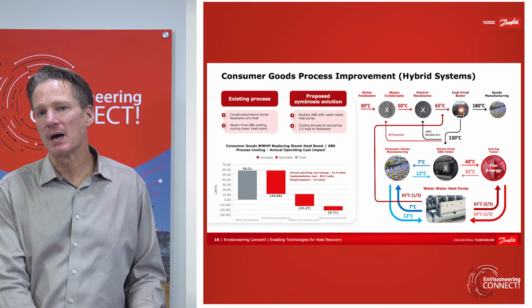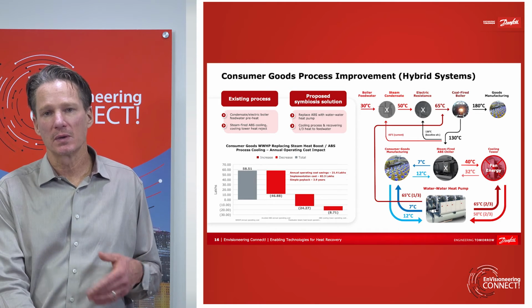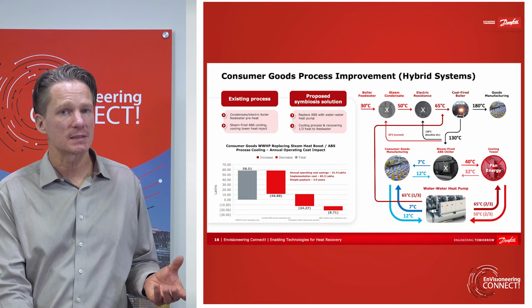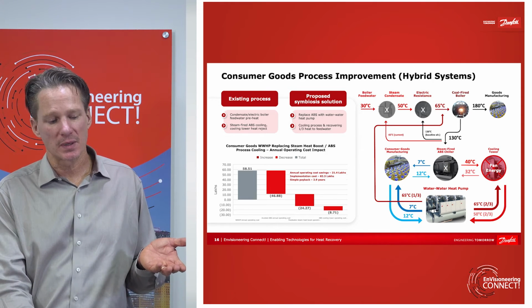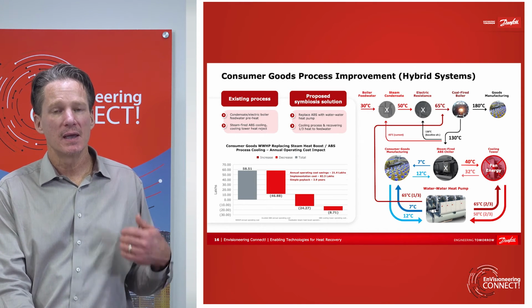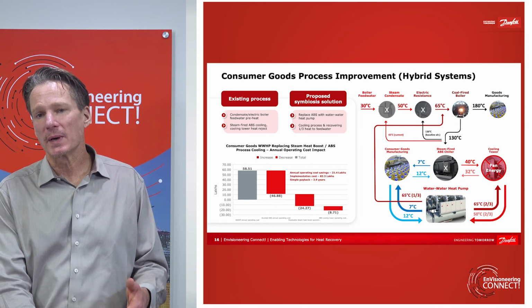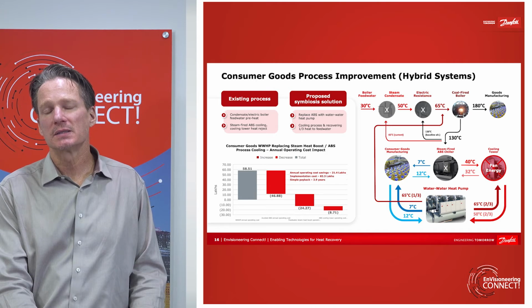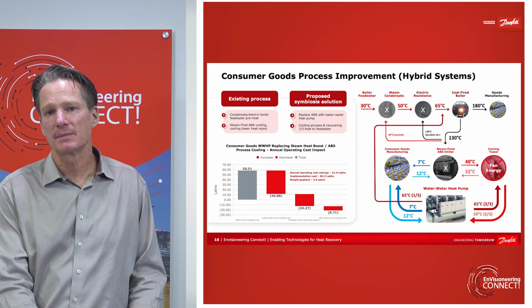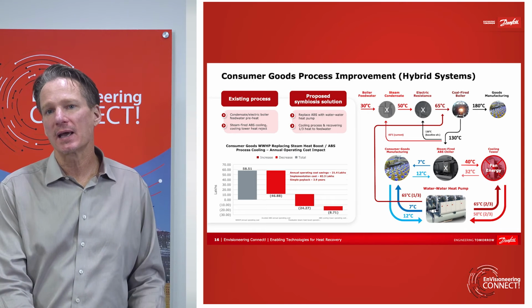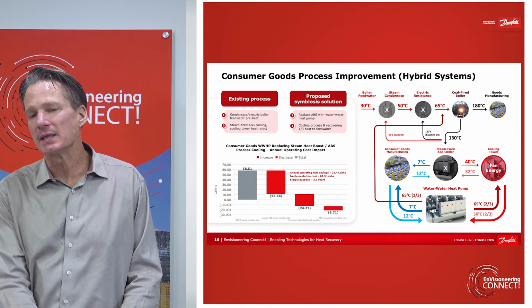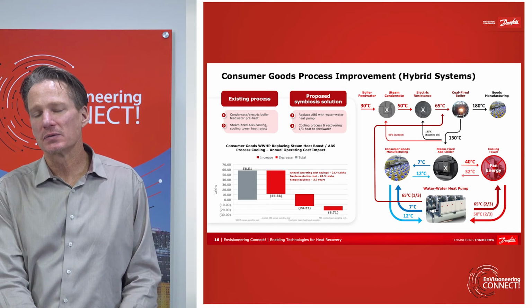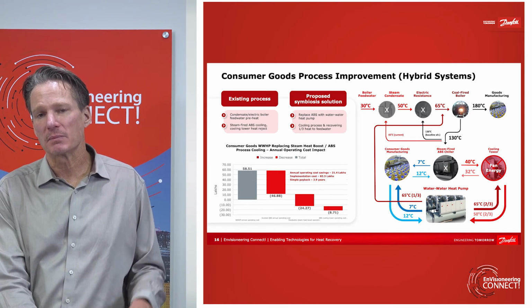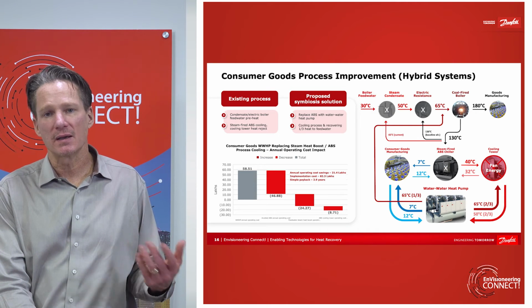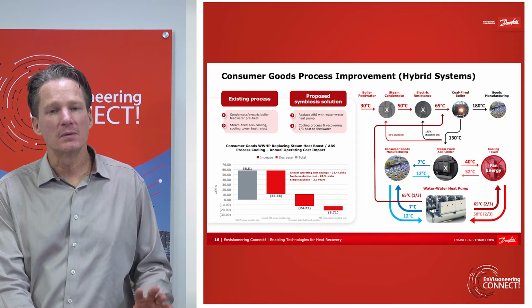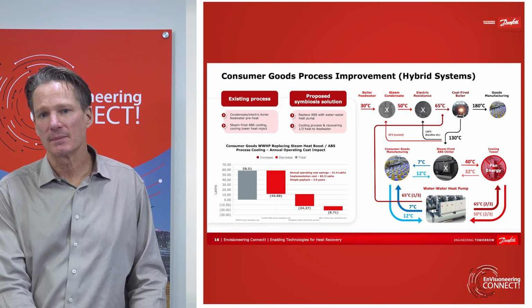And how we're doing this is by preheating the feed water that goes into the boiler. So every boiler system in general has a feed water system. And that boiler is going to operate more efficiently if you preheat the water that's going into it. So we're recovering the heat from that industrial process to preheat the feed water going into that system. That higher temperature that we're rejecting it at also allows them to take the rest of the heat that we can't utilize and send it through the cooling tower, but the cooling tower doesn't have to operate the fans now. So it decreases the energy usage based on that, no need to operate the cooling tower fans anymore as well.